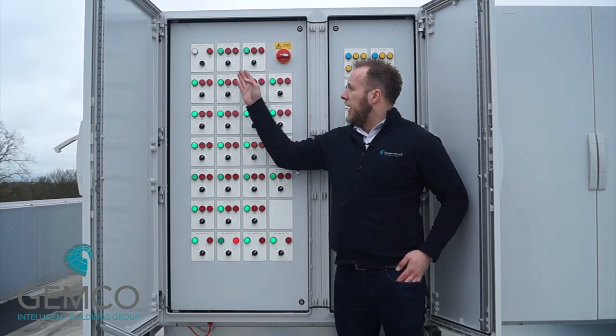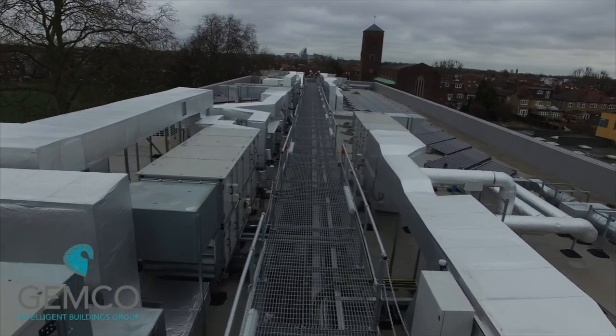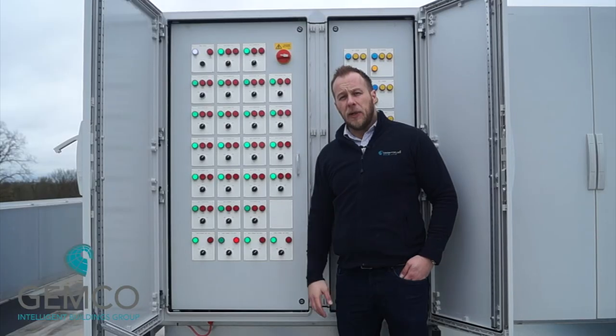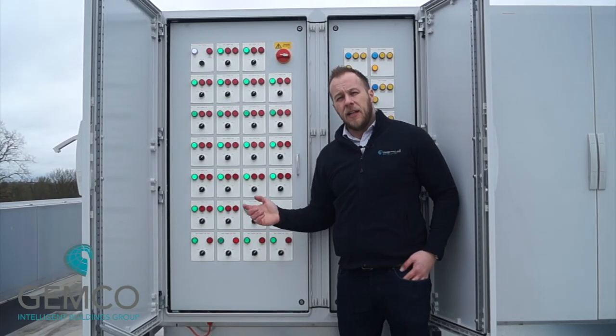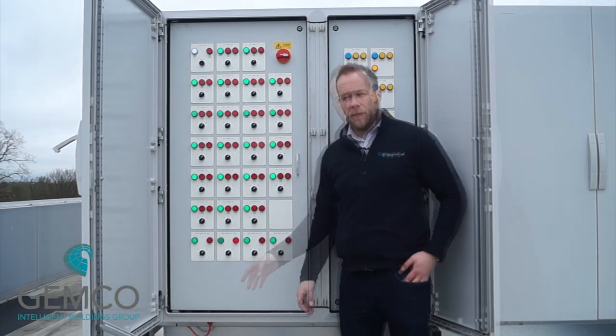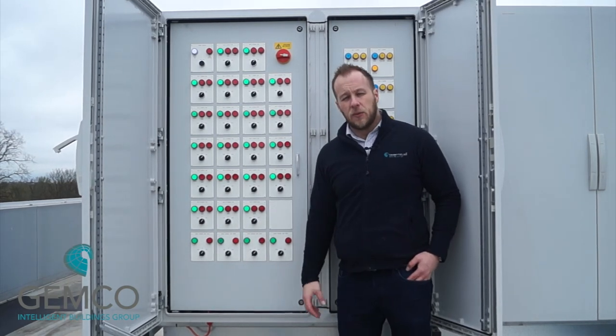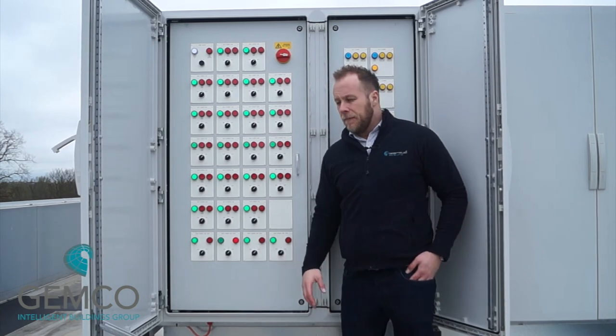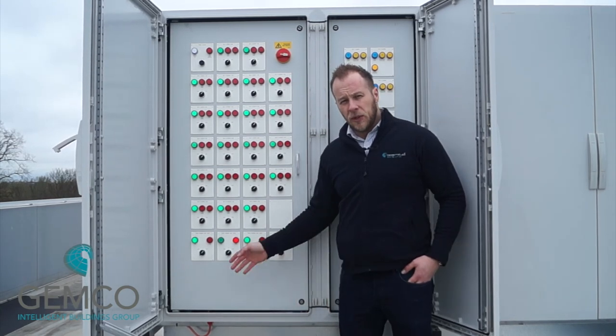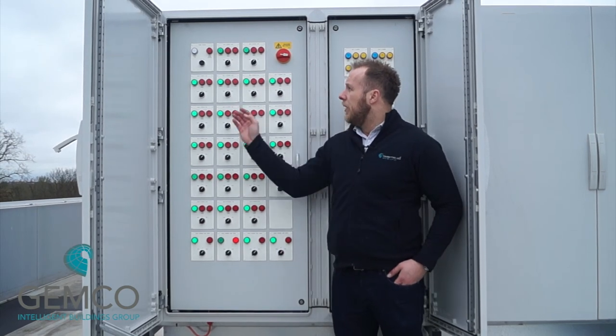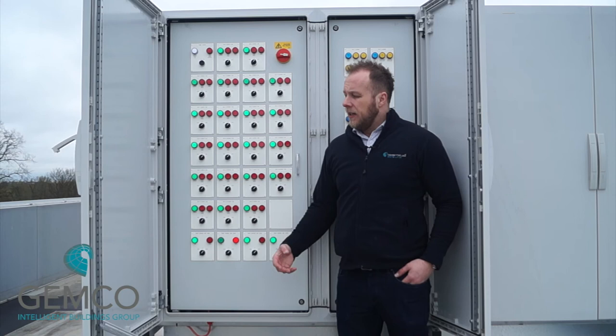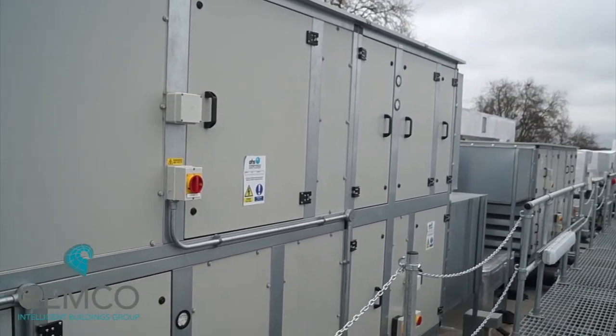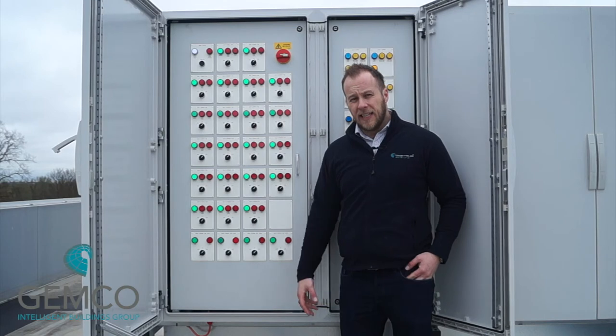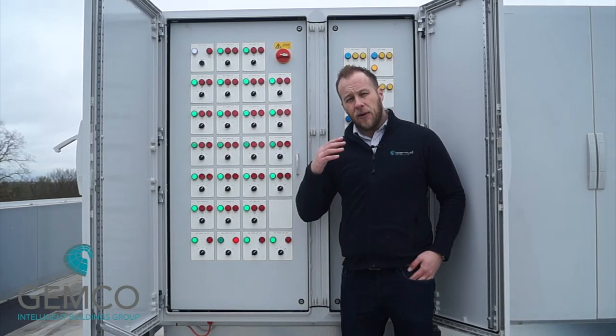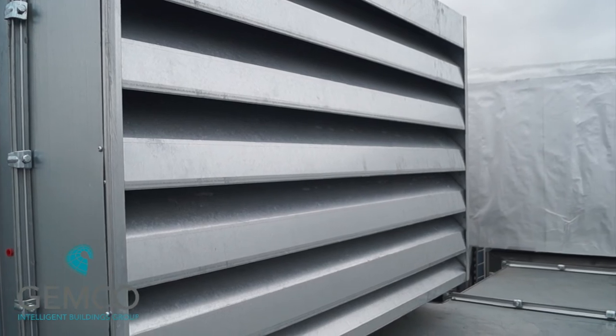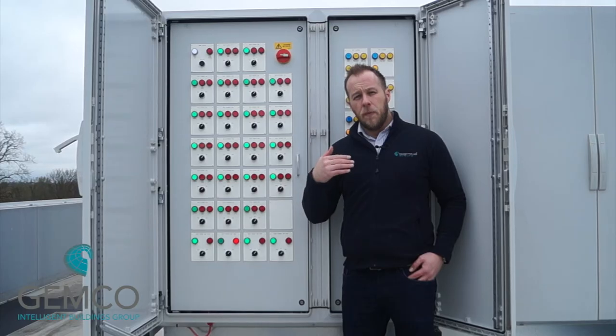And then moving on from that, you've got all of the air handling units. So there's 11 air handling units, 10 of which are supply and extract, and then number 11 is supply only. Now there's also 4 toilet extract fans which serve different toilets around the building, and those units are twin units, which I'll explain as we go down. So first of all, I'm going to go through the basic operation of an air handling unit. Now the air handling unit will be enabled. Once it's enabled, there'll be an inlet and outlet damper motor on a set of blades on each air handling unit which will begin to open.